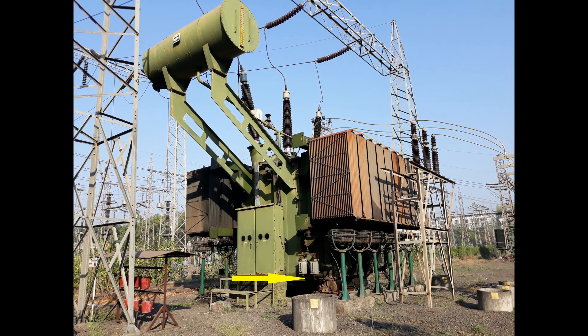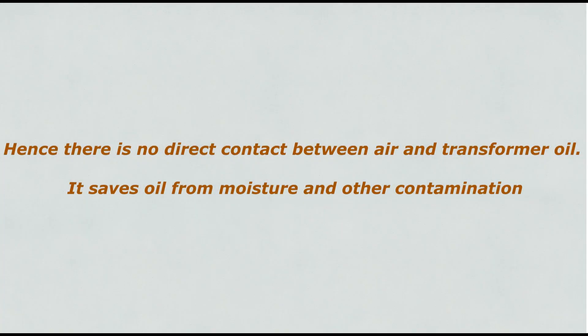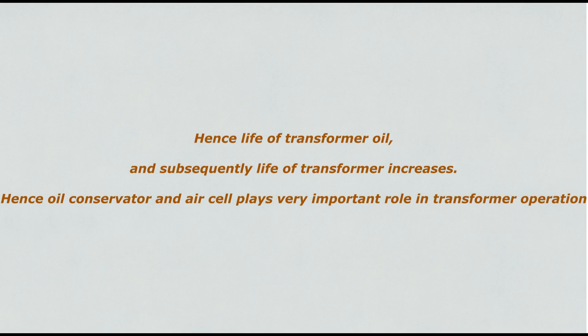When the transformer breathes in, that air gets accumulated in the air cell itself and the air cell expands. When the transformer breathes out, the same air goes out. Hence there is no direct contact between air and transformer oil. This saves oil from moisture and other contamination, and hence the life of transformer oil, and subsequently the life of the transformer, increases.